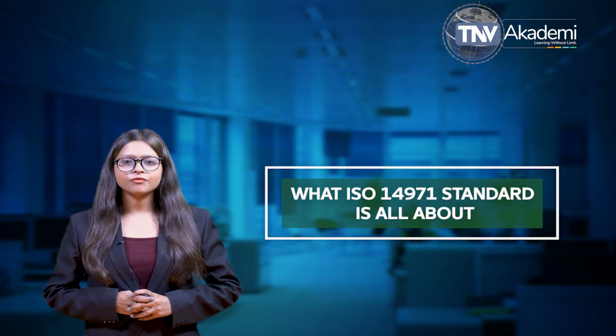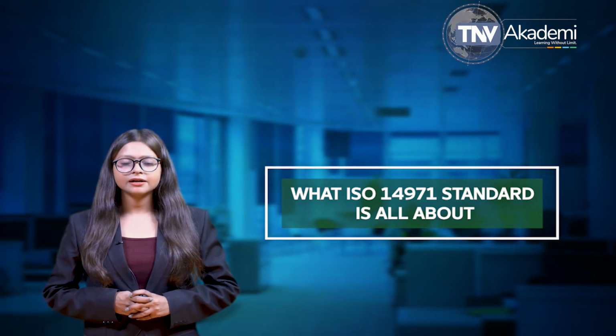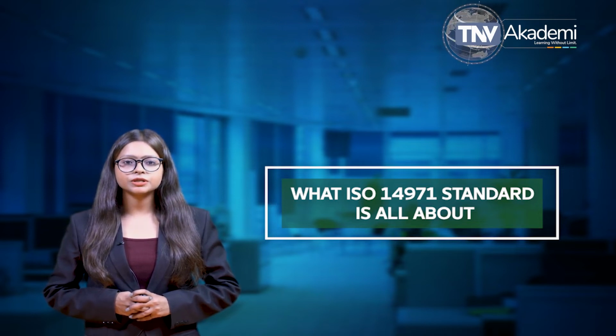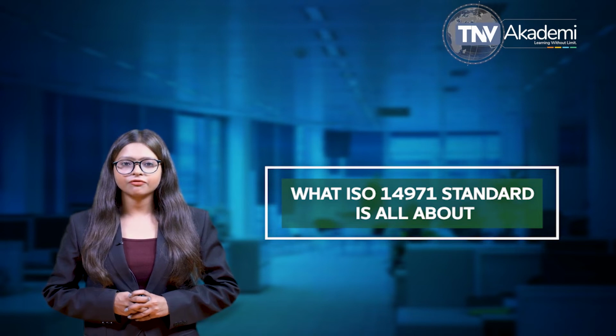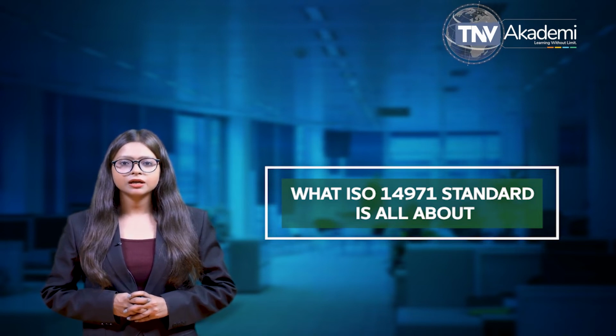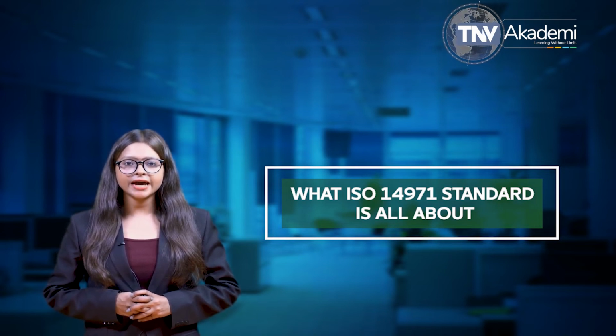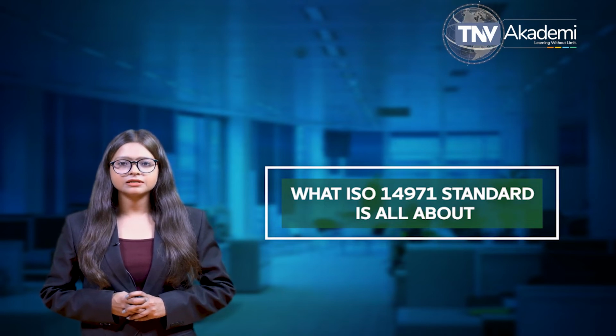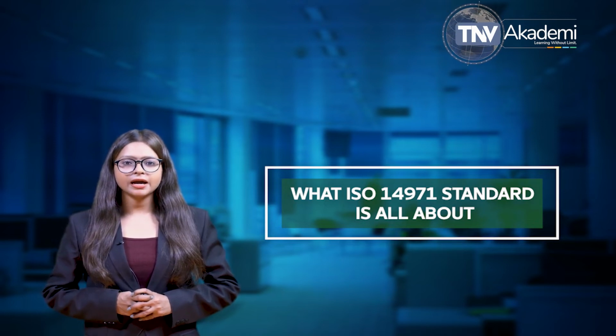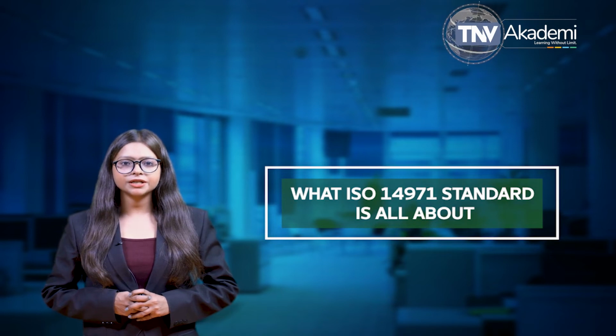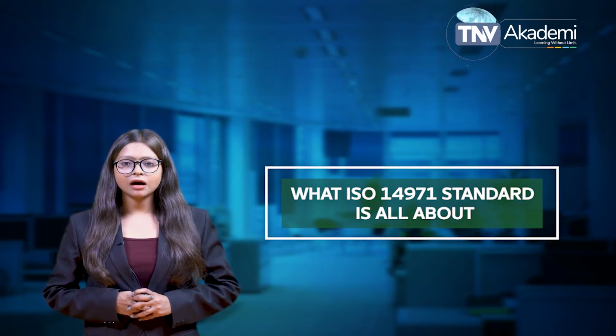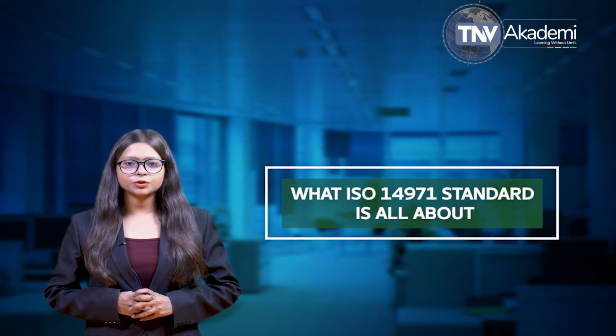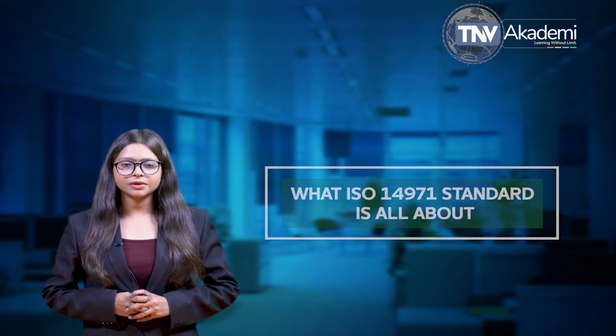The ISO 14971 standard requires manufacturers to establish objective criteria for risk acceptability but does not specify acceptable risk levels. Risk management can be an integral part of a quality management system. However, this standard does not require the manufacturer to have a quality management system in place.